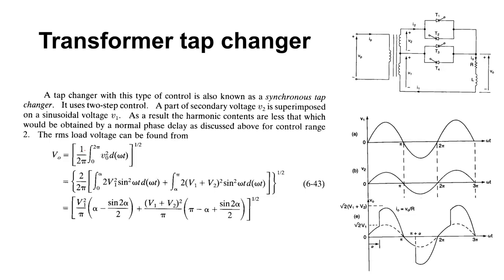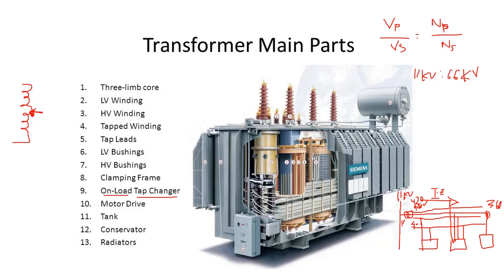Now if I recap the whole thing, the transformer tap changer changes the tap position of the transformer so that you can control the output voltage, and you can do that manually, that means using mechanical switches. There are 2 types of tap changers: the on-load and the off-load tap changers. With off-load tap changers you have to disconnect the load first, then physically go there and mechanically change the tap settings. So you have to turn the load off, so no current is flowing, and then physically go there and change the tap settings. Normally in the transformer, within this box, you have a wheel arrangement where you rotate this wheel to change the tap settings. That is what is done in the off-load arrangement.